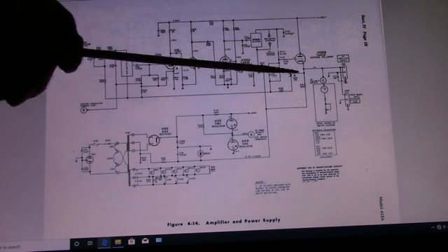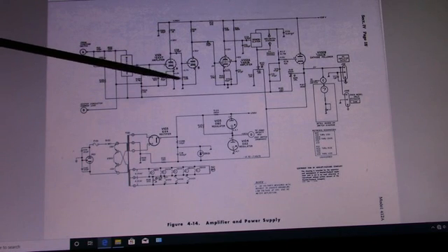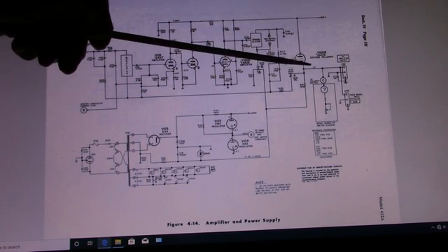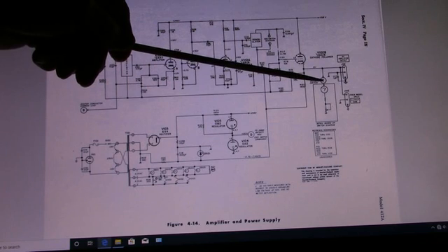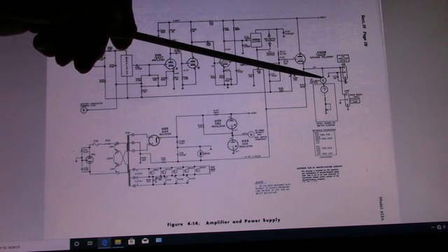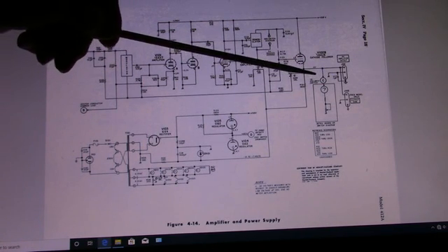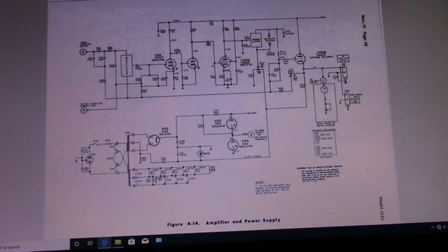Also at that point, you've got quite a bit of negative feedback to the input. I think it's about 50 dB of negative feedback that stabilizes the amplifier. The output also is connected at point C here. This is the polarity inversion switch where you can reverse the polarity for the volt and milliamp ranges here. And of course, here's the meter, gives you your output.